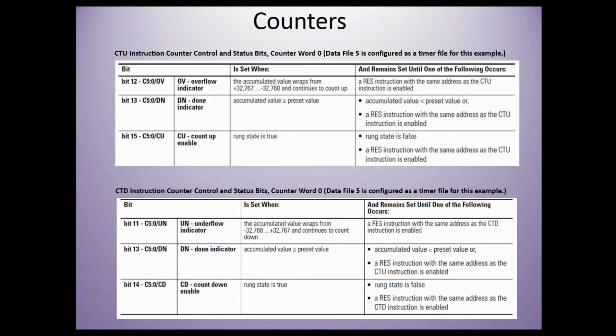Bit 15, which is CU the count up bit, this is true whenever the rung status is true and it goes false whenever the rung status is false. Also, if at the same time the reset instruction is true, it would also be false.